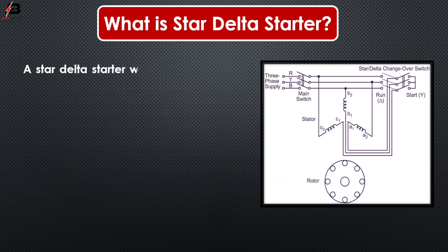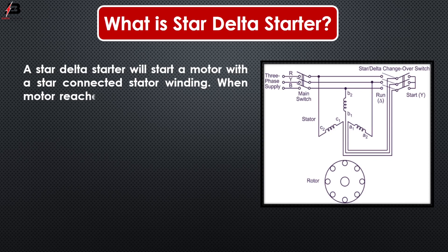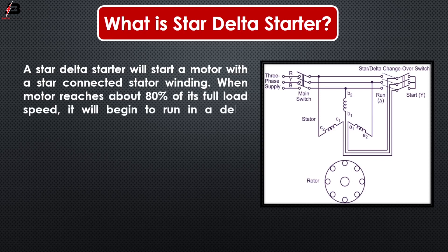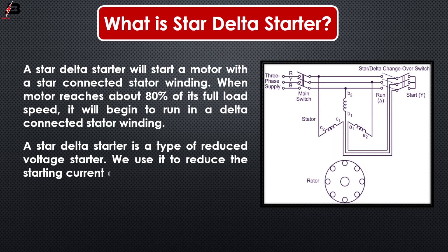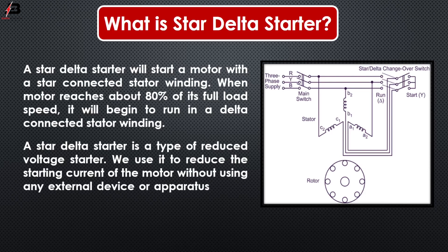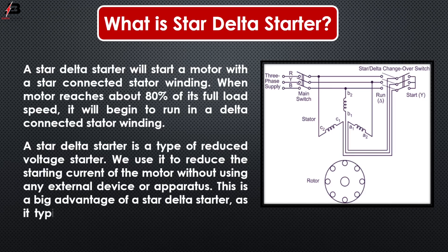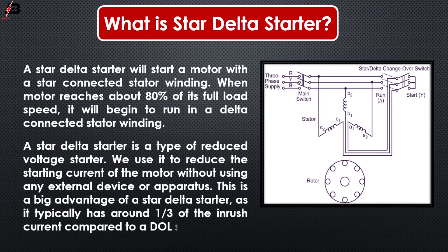A star delta starter will start a motor with a star connected stator winding. When the motor reaches about 80% of its full load speed, it will then run in a delta connected stator winding. A star delta starter is a type of reduced voltage starter. We use it to reduce the starting current of the motor without using any external device or apparatus. This gives it around 1/3 of the inrush current compared to a DOL starter.